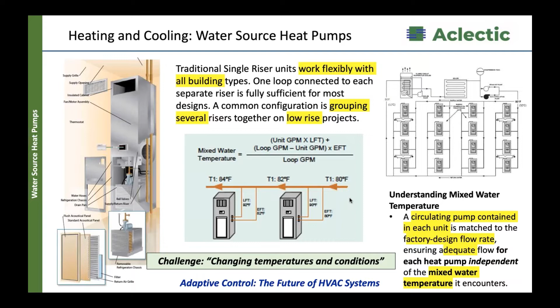What we're highlighting in the middle here is an example of looking at a microcosm of just two units. The water entering at 80 degrees on the unit on the right goes through that unit. As it does, it extracts some of the heat energy in that room, transfers that heat energy to the fluid, and passes it out at 82 degrees over to the next one, which now gets 82 coming in. It extracts heat from the room, adds it to that source of water or refrigerant, and sends it out at 84. If you imagine this replicated dozens of times, the units on the upper right versus the upper left are not seeing the same thing, and yet they're operating in the same way.